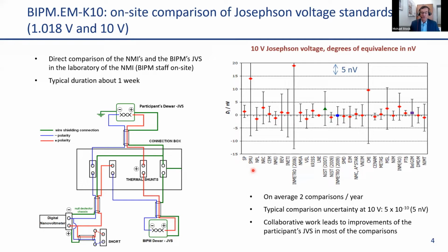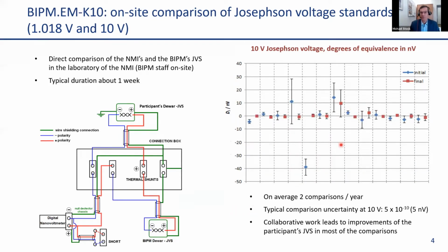Now, what we've quite often found is that this collaborative work between the BIPM staff and the local staff leads to some improvements of the participants' Josephson voltage standards. So Gerd Rietveld mentioned that we do some CBKT work. So these comparisons have, in fact, an aspect of knowledge transfer. And this you can see here. For some comparisons where I have not identified the institutes, you see in blue the initial result, which was obtained directly at the start of the comparison, and at the end of the week, the final result in red. And you see that there are, in some cases, quite dramatic improvements either in the value or in the uncertainty, and in many cases, even still quite some substantial improvements.